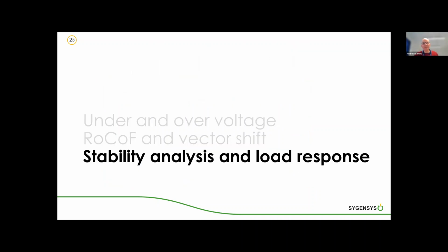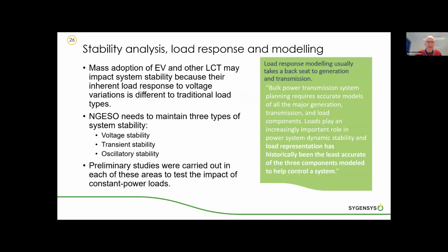So the third area of detail we looked at in this work package 2 was stability analysis and load response. The mass adoption of electric vehicles and other low carbon technologies may impact system stability because their inherent load response to voltage variations is different to traditional load types. We're not talking here about intentional demand side response. This is just the behavior of the load with voltage. We're all familiar with the behavior of traditional loads, so resistive heating, tungsten lighting, induction motors, things like that. But these loads will behave differently, and there will be a lot of them in the future.